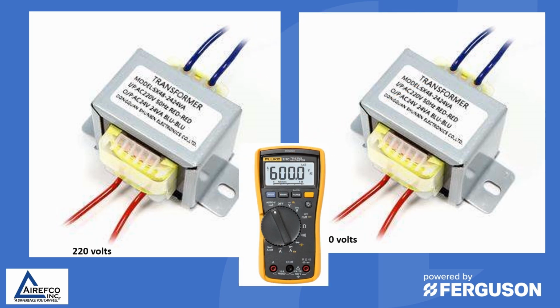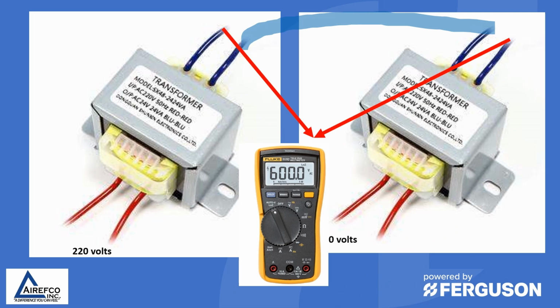So if you do get a spark, the next thing you want to do is take the other two blue wires and tie them together, and then take your voltmeter and check the voltage between those blue wires that you have taken apart. And if you have 0 voltage, then the transformers are tied together in the proper manner and they're properly phased.